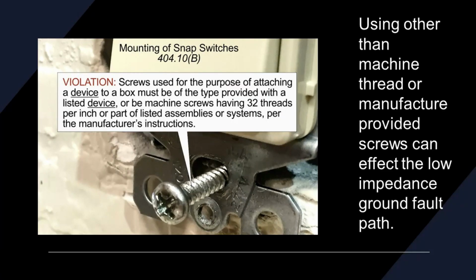This is the violation I'm talking about. These threads are too thick. They cannot make it. Two threads will not be in contact at the same time with that box, so it's too far. Too far apart, not enough solid contact with the box. You have affected the low impedance ground fault. This is the high impedance ground fault path now.